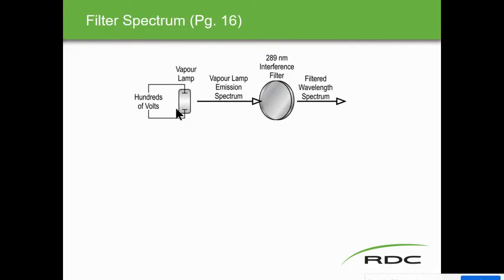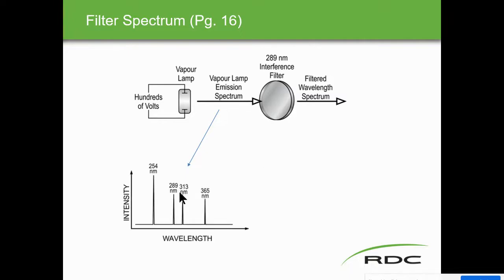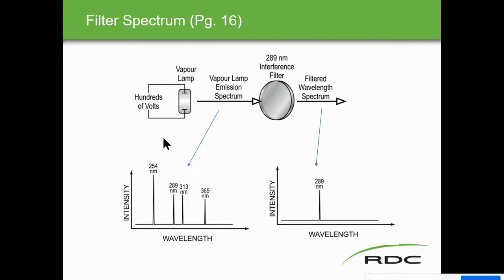An example of a filter spectrum: a mercury vapor lamp emits line spectra at 254, 289, 313, and 365 nanometer wavelengths. Using a 289 nm interference filter, all other wavelengths are filtered out, and only the 289 nm wavelength of interest passes through to the sample cell.